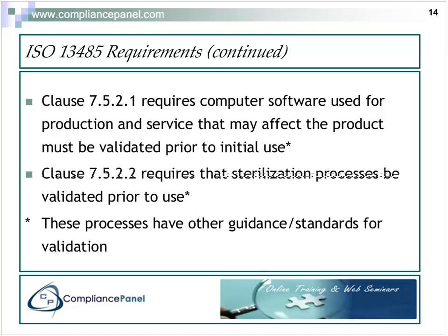7.5.2.1 also requires that computer software used for production and service that may affect the product must be validated prior to initial use. And there's one on sterilization, of course. 7.5.2.2 does require that sterilization processes be validated prior to use, and that's a general requirement in the FDA as well.